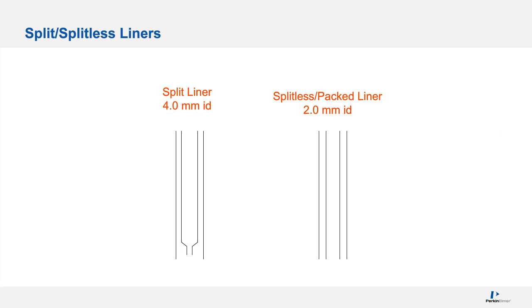Typically, people for splitless injections use a 2 millimeter liner, but you absolutely can use a split 4 millimeter liner in splitless mode. You cannot use a splitless liner for split injections. Split injections require mixing. I'm not explaining this as well as I can. I know. I'm sorry, folks. It requires some equilibration in the liner before injection. So a straight through liner will not give you precision in the split mode.